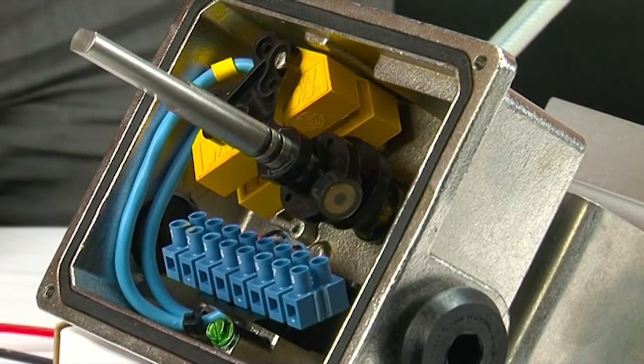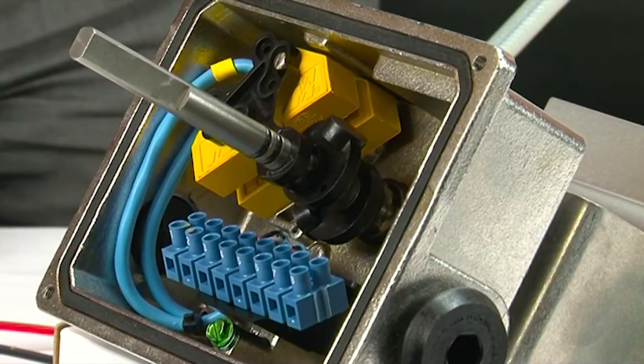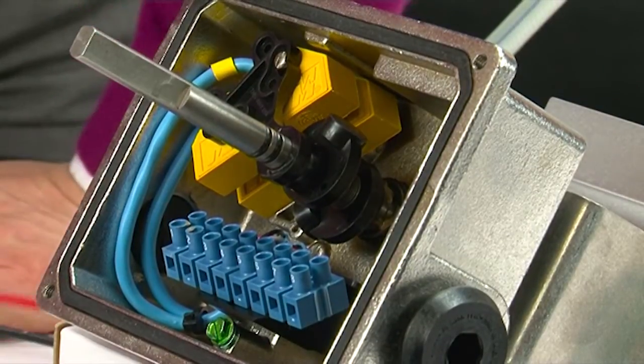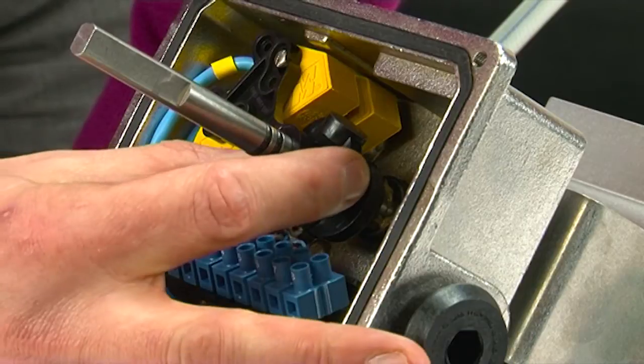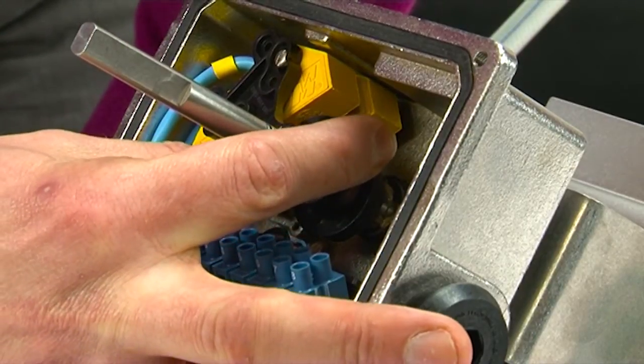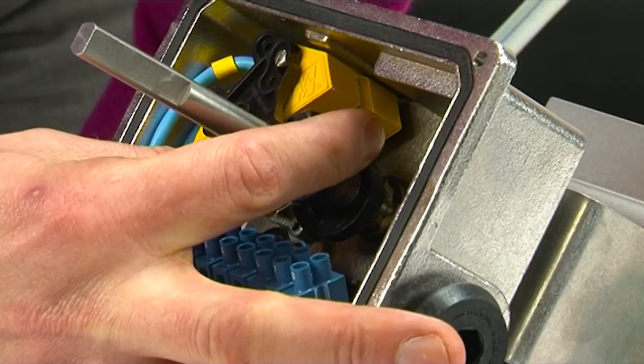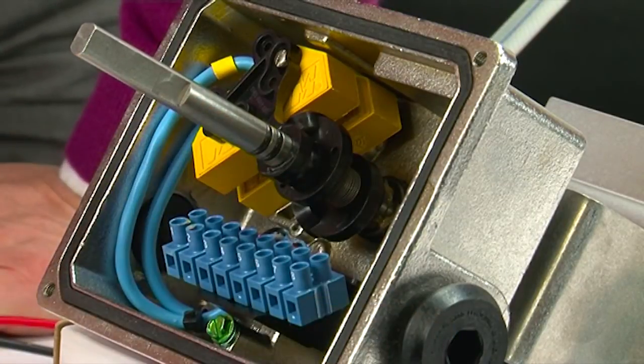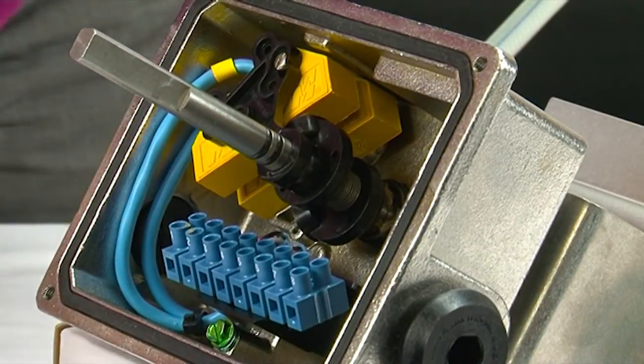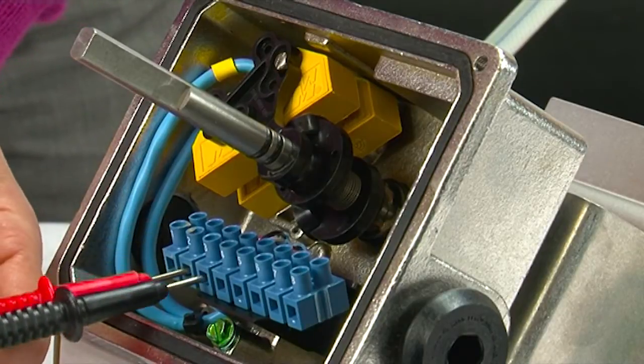The next thing to do is to stroke the actuator into the open position and set the top switch. Again this can be done by depressing the cam, rotating the striker in front of the sensor and releasing so it locks back in place, and then verifying the reading using the meter.